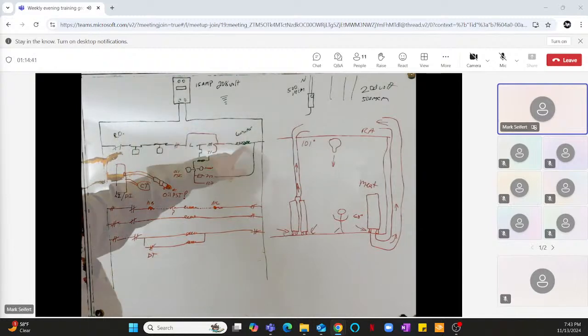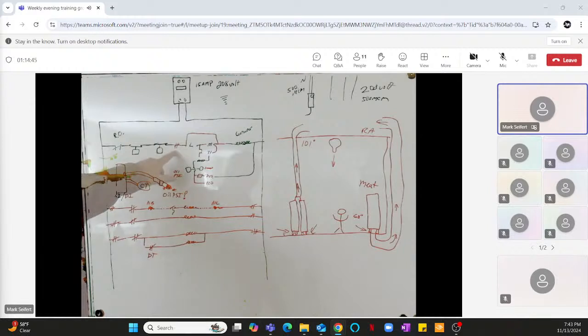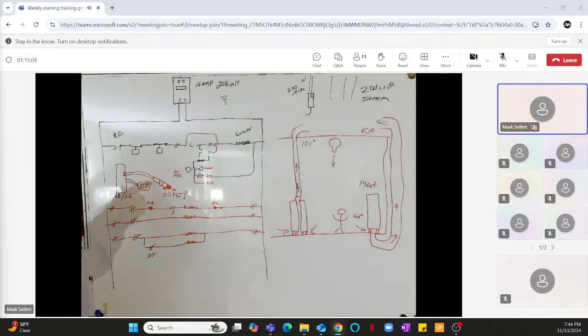It just knows the RO is telling it to run. So trip breaker, coil open, whatever that, I don't remember what that was. Oh, overload, high pressure, low pressure, blown fuse, right here, blown fuse. All that will make the contactor not come on and have no oil pressure, and it'll trip on oil. So if you are tripped on oil and it does not have a CT, it doesn't necessarily mean that it's got no oil pressure. Well, it does mean it's got no oil pressure. It doesn't mean the compressor was running. So just because it's tripped on oil does not necessarily mean it's an oil problem when it comes to the controller. I'd say unless there's a CT, but the CT could break. Anything could break. You've got to remember, anything could not be working in the system.